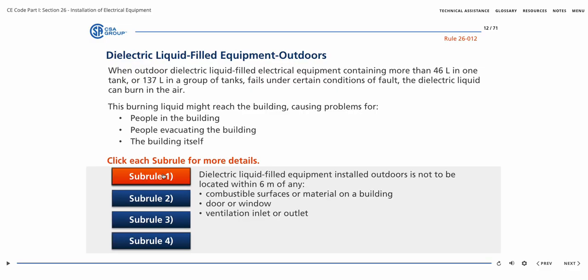Except as permitted by Sub-Rule 3, Rule 26-012 requires that dielectric liquid-filled electrical equipment containing more than 46 liters in one tank or 137 liters in a group of tanks, and installed outdoors, shall not be located within 6 meters of any combustible surfaces or material on a building, door or window, or ventilation inlet or outlet.